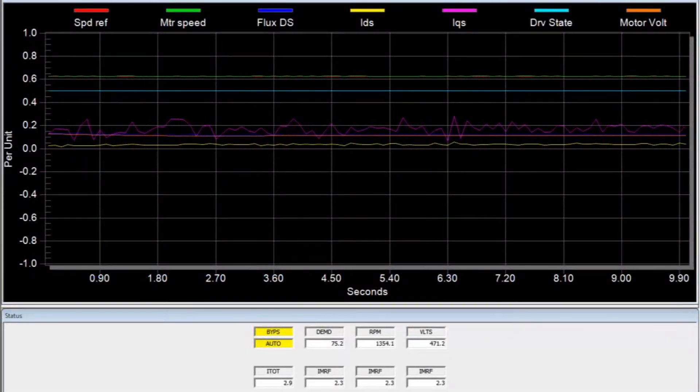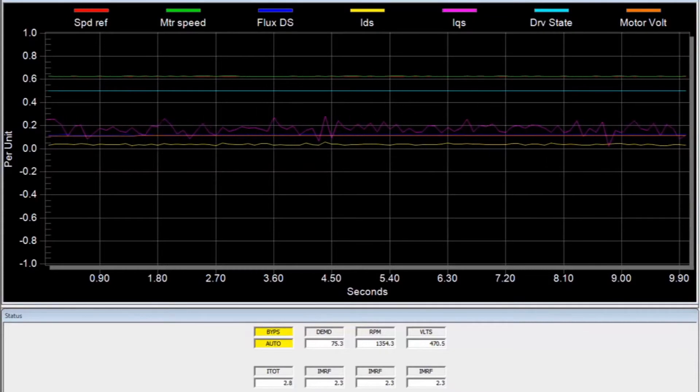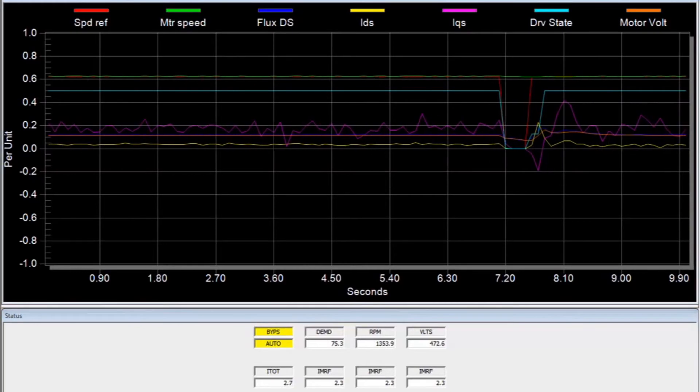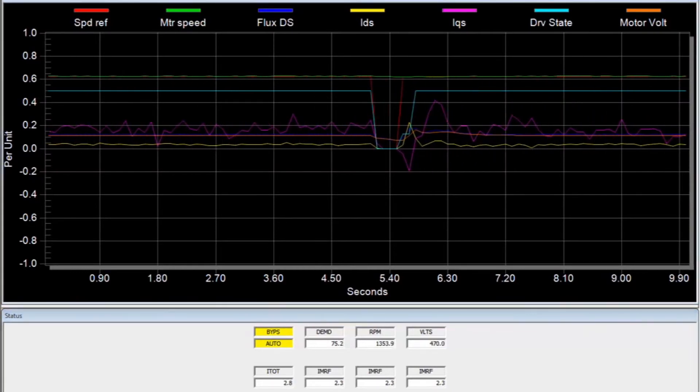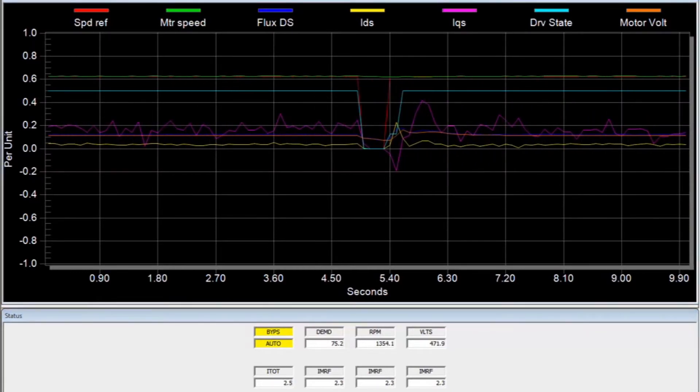Here you can see that the drive is running under normal conditions. Now you can see the cell fault and then be placed into cell bypass. The red speed reference and light blue drive state lines have dropped to zero as the drive reconfigures itself around the failed cell.